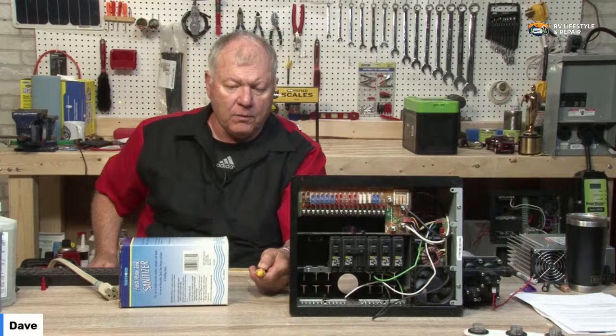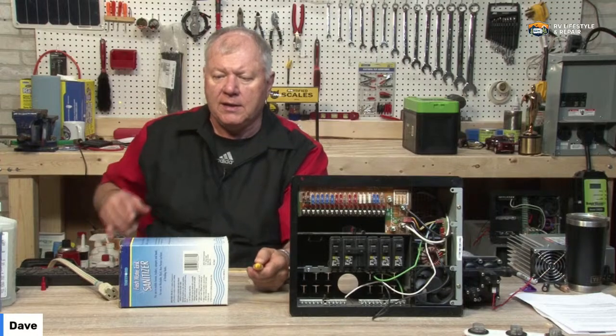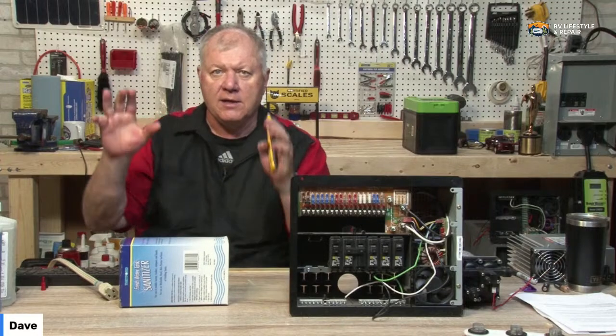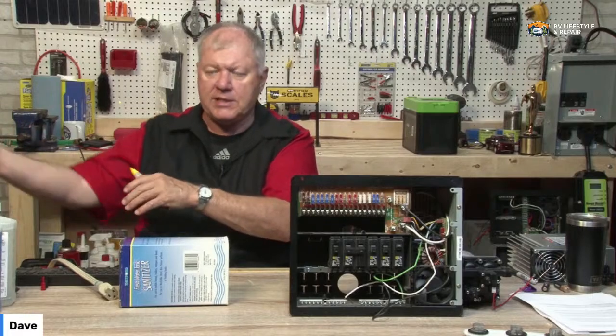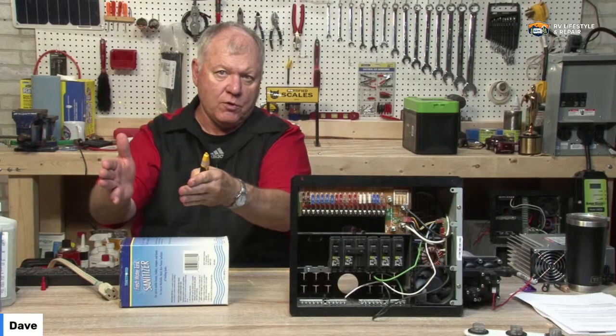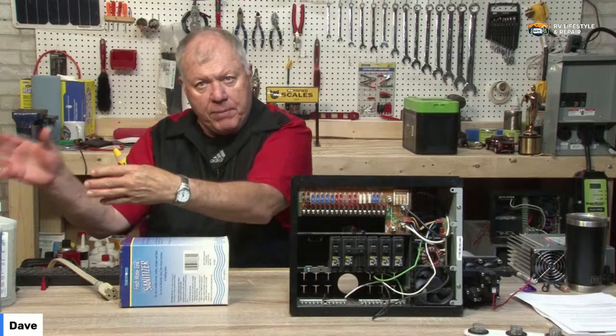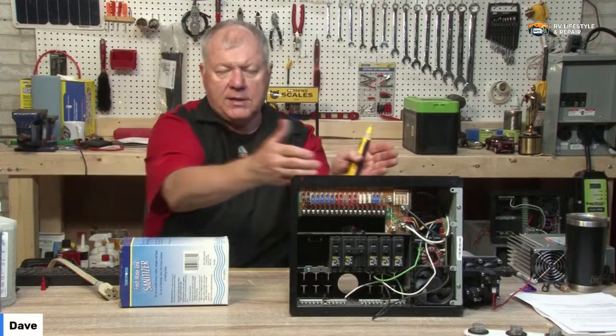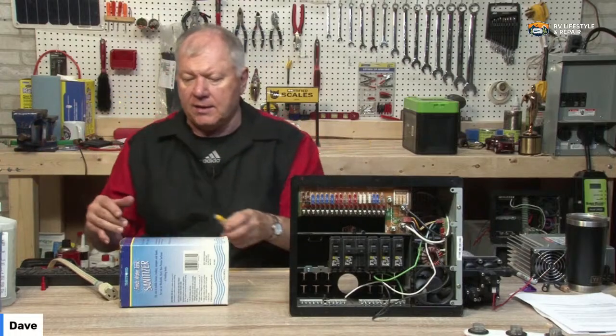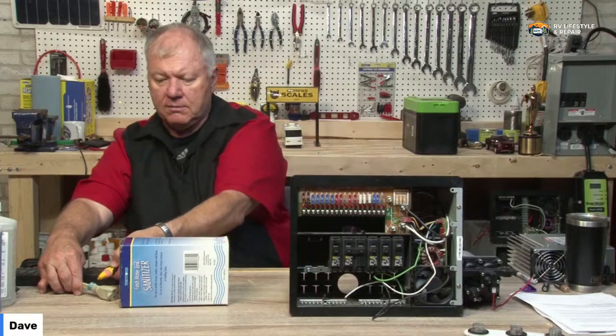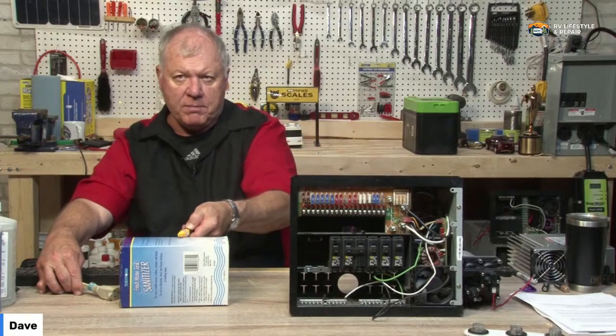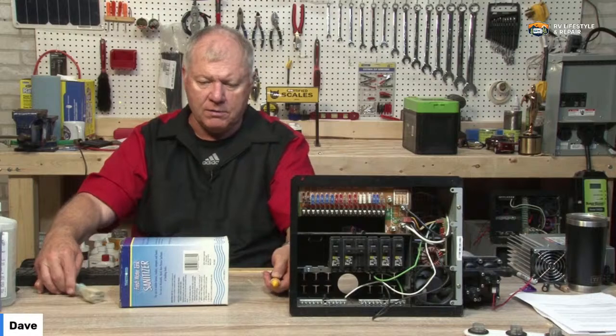When the generator is running, this automatically defaults to generator. So when it senses power from the generator, that switch is going to go grab power from the generator and take it to here. So if I have power coming in here, I've got power in the box, but I don't have power.